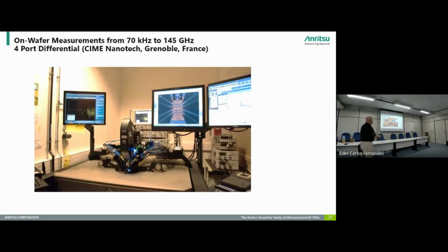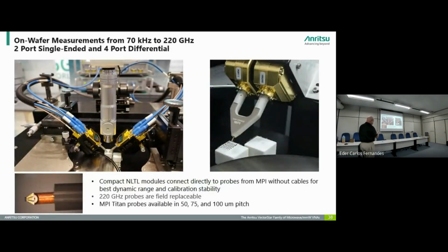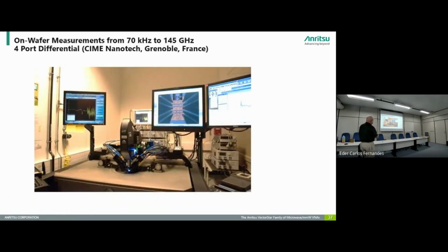The table, what you see here, that's all part of the probe station. This section here is a large prober. This is like a 300 millimeter, I believe. This surface here is what's called the platen, and it's part of the probe station. You can kind of see the Cascade logo right there, the FormFactor as they're referred to now. We're compatible with any of the probe stations out there, because a probe station is essentially a mechanical fixture, a very high precision mechanical fixture. There's no reason why we can't adapt to any of the existing probe stations out there.